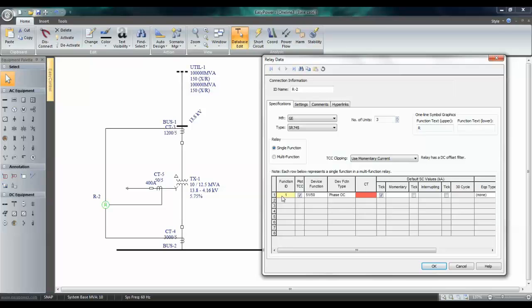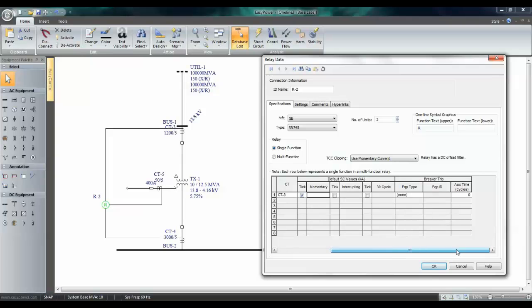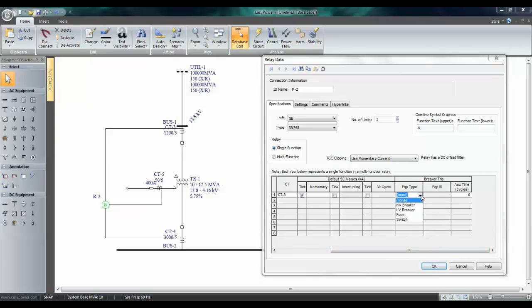The function ID. The first device function, we shall call this 5150, for overcurrent relay on the primary side. Select the CT. So, this is CT number three. And the device to trip is HV breaker.